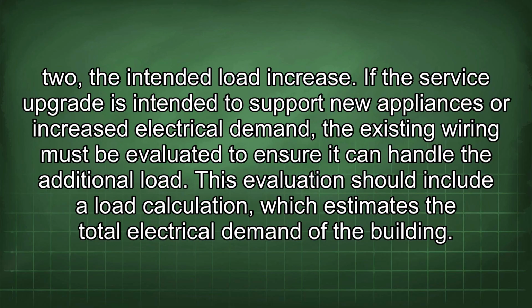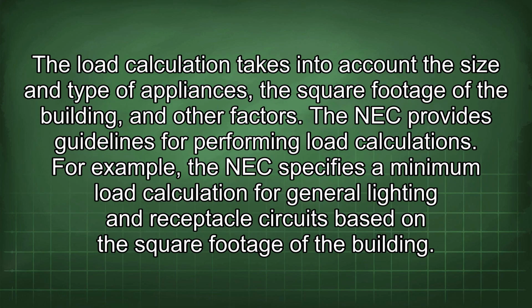If the service upgrade is intended to support new appliances or increased electrical demand, the existing wiring must be evaluated to ensure it can handle the additional load. This evaluation should include a load calculation, which estimates the total electrical demand of the building. The load calculation takes into account the size and type of appliances, the square footage of the building, and other factors. The NEC provides guidelines for performing load calculations.